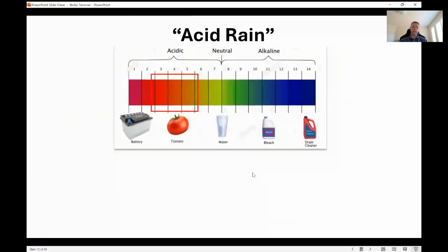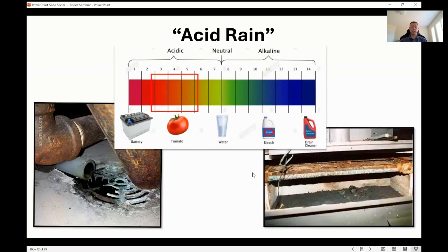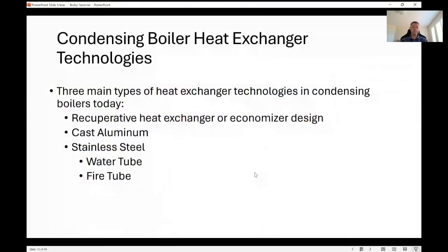So when you do condense, I think everybody's aware that condensate is water, but it's very acidic water. Generally that pH is around 3.5 or so. It's very low, and that's going to rot things out. Here's a picture of a copper tube boiler after being in a condensing environment. It basically starts rotting it out, or rotting out the burners. I don't want to see what the vent looked like here. So that's a little bit about condensing versus non-condensing. I think everybody these days is pretty much putting in condensing boilers, so I do want to focus on that a bit.